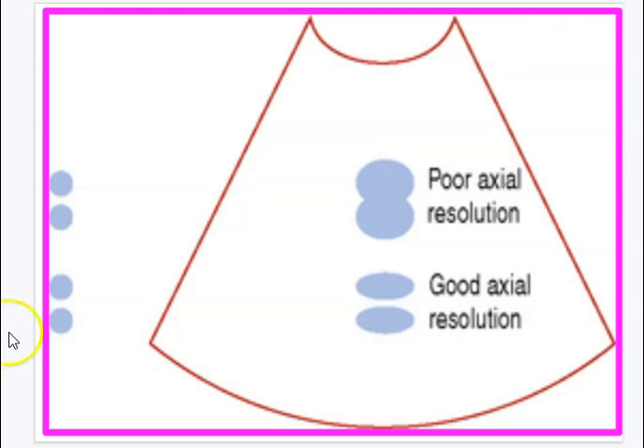So here's an axial resolution scan, and we can see that we have poor resolution here. Our wavelength isn't short enough, the pulse length isn't short enough, and our frequency isn't high enough to differentiate between these two objects. However, if we switch to a higher frequency transducer, we can get better resolution right here. In the separation of these two objects, we can see these objects aren't one, but actually two.